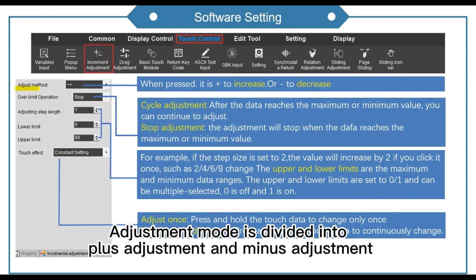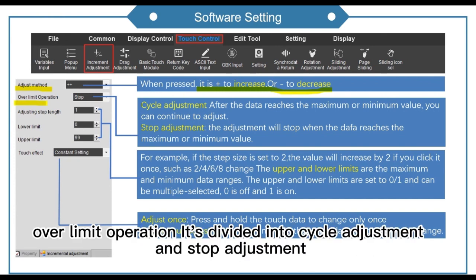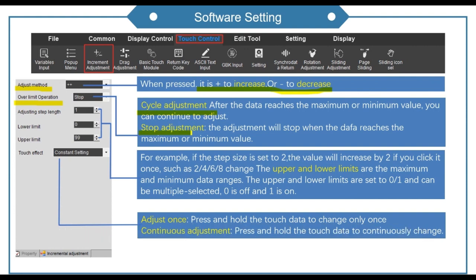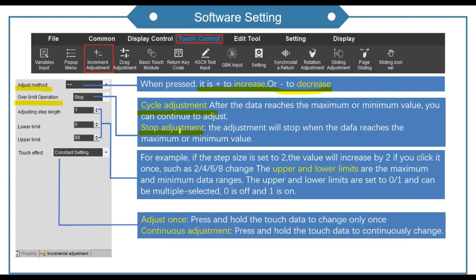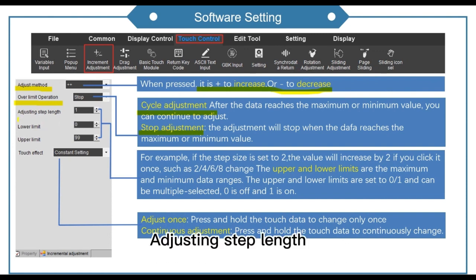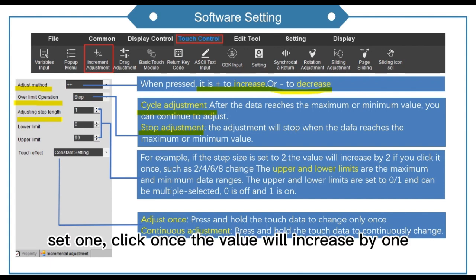Adjustment mode is divided into plus adjustment and minus adjustment. Over limit operation is divided into cycle adjustment and stop adjustment. Here we choose stop adjustment — the adjustment will stop when the value reaches the maximum or minimum value. Adjusting step length: set 1, so click once and the value will increase by 1.